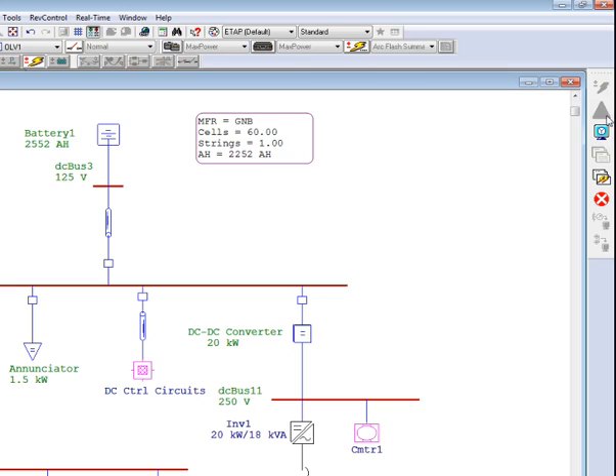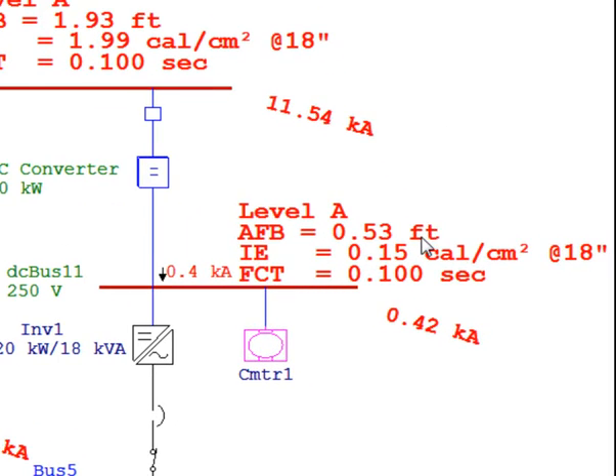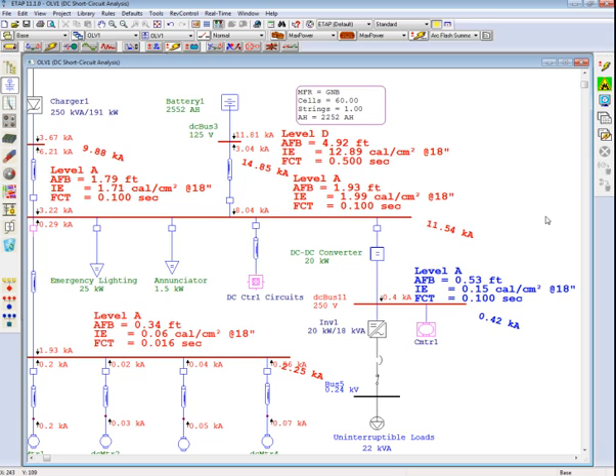Utilizing the maximum power method at this location, a fault clearing time of 0.1 seconds and an incident energy of 0.15 calories per centimeter squared is displayed on the one-line. That illustrates the main difference between the Stokes and Oppenlander method and the Paukert method compared to the maximum power method. The Stokes and Oppenlander method can let the user know if the arc can occur and be sustained, while the maximum power method always predicts some kind of incident energy.